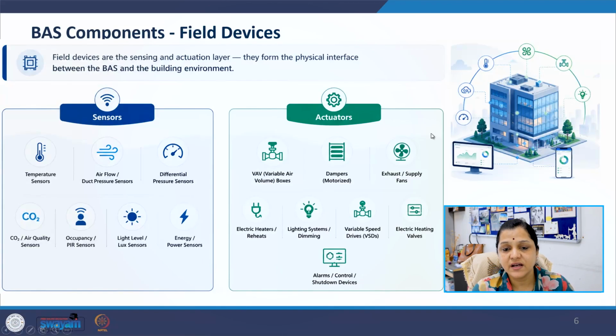Then the actuators. Actuators perform physical actions in response to control commands. Examples include VAV boxes and control valves. Dampers, actuators, lighting dimmers, relay panels, and variable speed drives. Electric heating elements and access control devices may also operate as actuators within building automation environment. Together, sensors and actuators create the physical feedback loop that allows intelligent building controls.